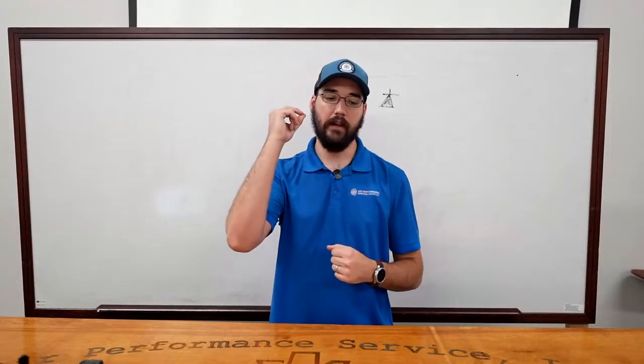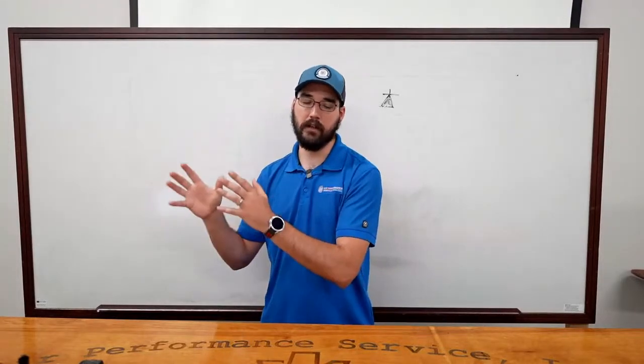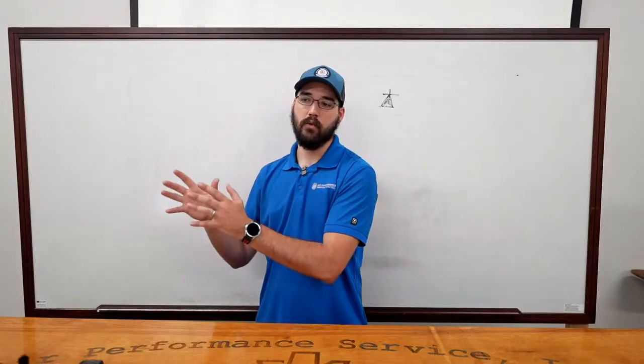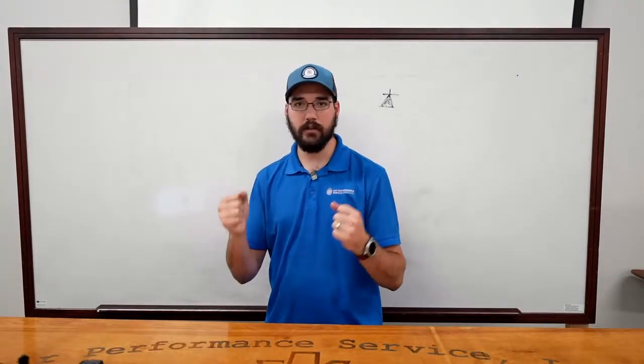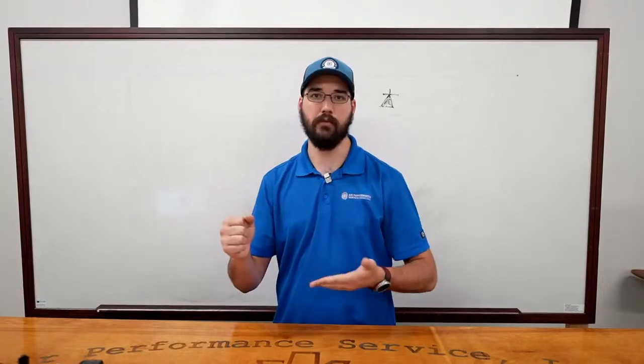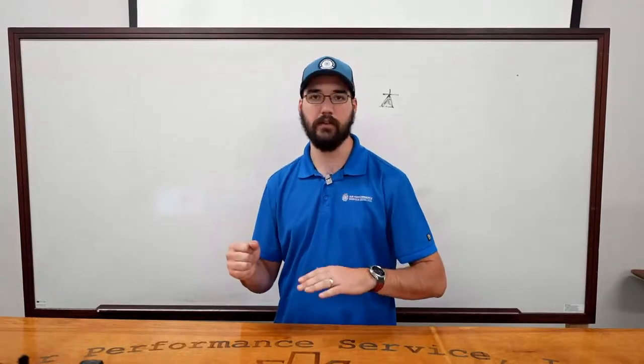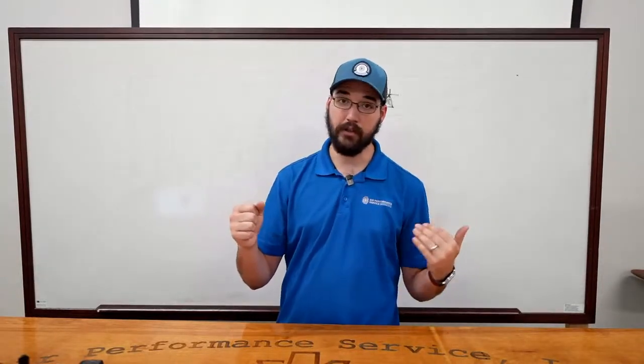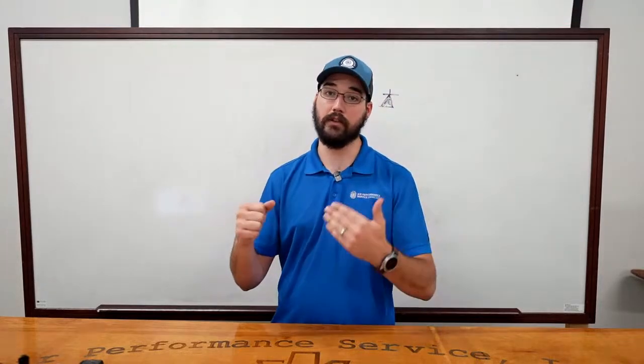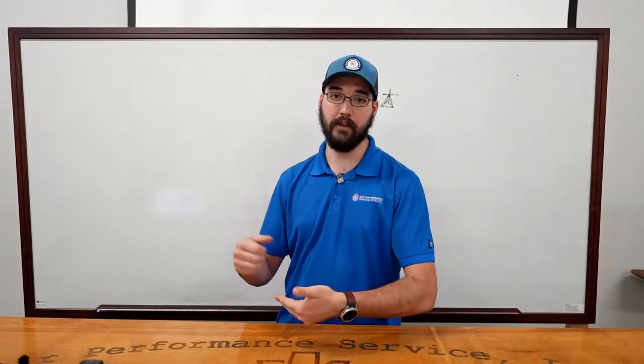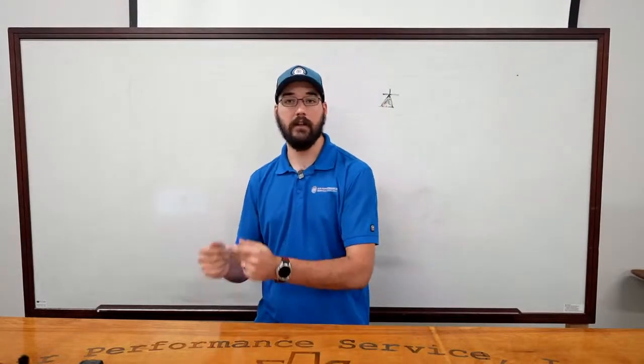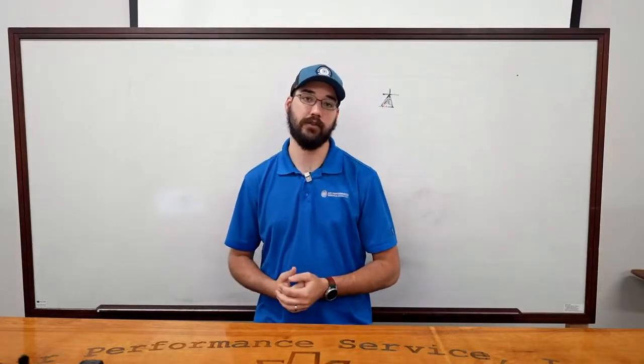So just trust the manual, because at the end of the day, what I do is take the manual and literally show it to the customer and walk them through it. Okay, this is the procedure. This is what it says. I went through all these checks and it said everything was good. I turned it back on, that was the next step. I ran it for a couple of minutes, and it immediately triggers back out and we get another trip.